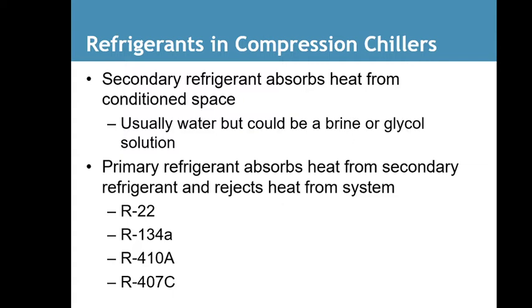Refrigerants in compression chillers. The secondary refrigerant absorbs heat from the conditioned space. It is usually water, but can be a cooled brine or glycol solution. The primary refrigerant absorbs the heat from the secondary refrigerant and rejects the heat from the system. They use R22, 134A, 410A, and 407C. Those are very common refrigerants in any commercial refrigeration or air conditioning system.